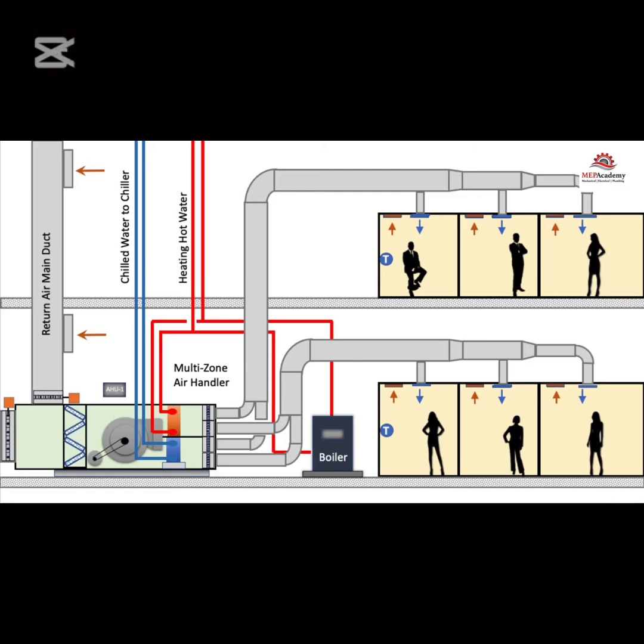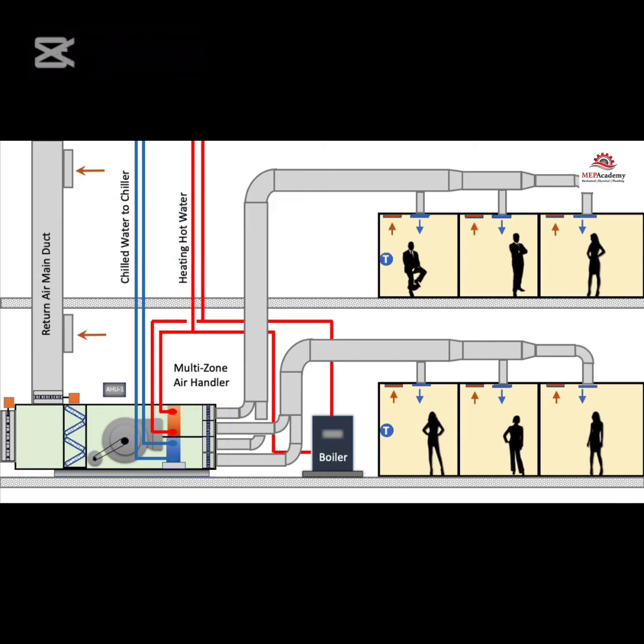This is a multi-zone air handling unit. Each of the zones has a hot and cold deck damper at the air handler unit, which is different than the dual duct air handler we just showed you. Each zone has its own supply air damper at the heating coil and another at the cooling coil.